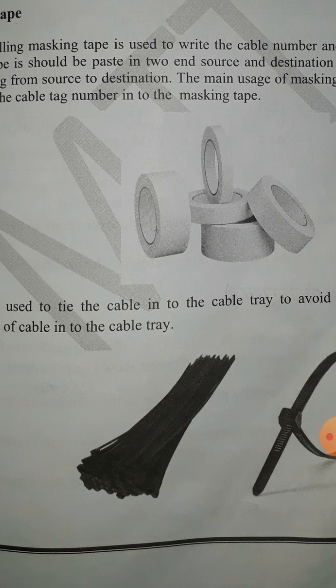Then another person checks again after 5 meters for overlap. So every 5 to 6 meters, a different worker checks, and if it's okay, you tighten it and continue serially to the end of the cable.